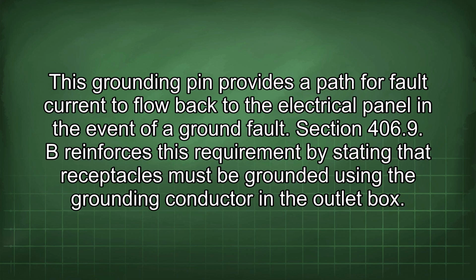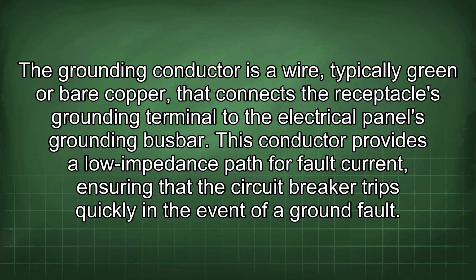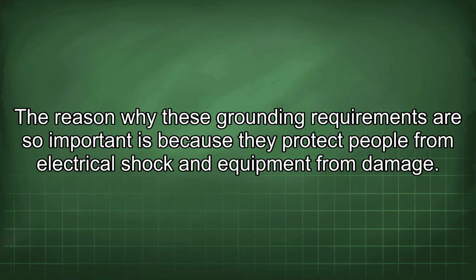Section 406.9 B reinforces this requirement by stating that receptacles must be grounded using the grounding conductor in the outlet box. The grounding conductor is a wire, typically green or bare copper, that connects the receptacle's grounding terminal to the electrical panel's grounding busbar. This conductor provides a low impedance path for fault current, ensuring that the circuit breaker trips quickly in the event of a ground fault. The reason why these grounding requirements are so important is because they protect people from electrical shock and equipment from damage.